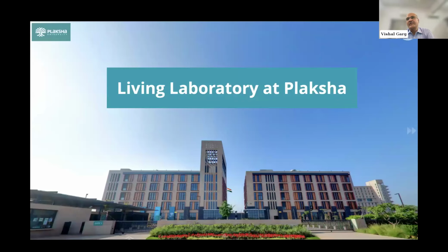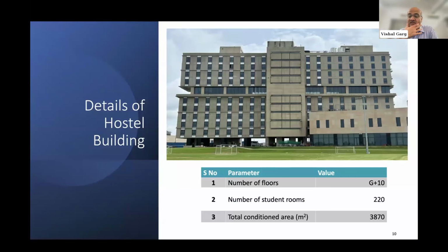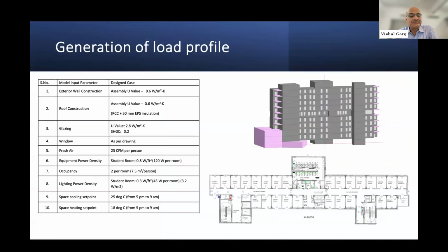Now, so we realize that yes, putting a district cooling kind of a system in residential can substantially bring down the installed capacity of chiller. Now we shifted our focus to what will happen if we provide a thermal storage system and shift the charging of the thermal storage to 100% daytime. So we took this hostel at Plaksha University. This is a G plus 10 floors hostel. It has 220 rooms and the total conditioned area is 3,870 square meters. It can accommodate about 440 students.